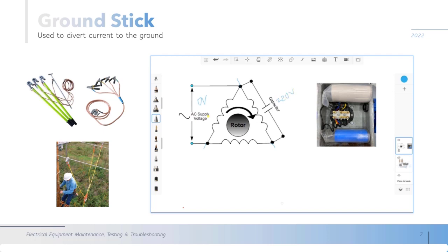If the voltage applied was 220 volts, there will be 220 volts, but only for a certain amount of time, because the voltage will be decreasing due to the circulating currents from the capacitor to these windings. So this voltage in time will be decreasing, but if you touch immediately after you open this voltage in the terminals, you will get electrocuted.